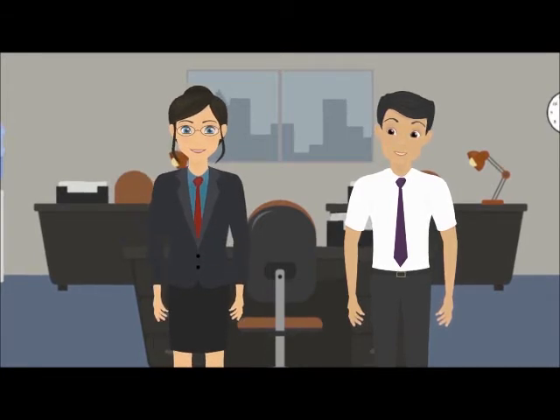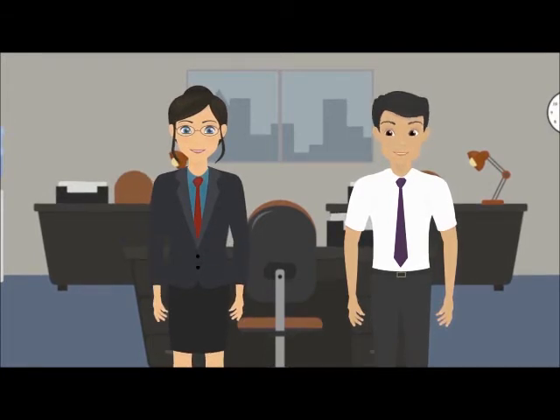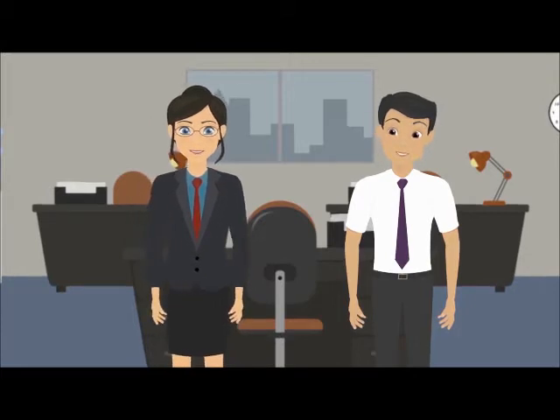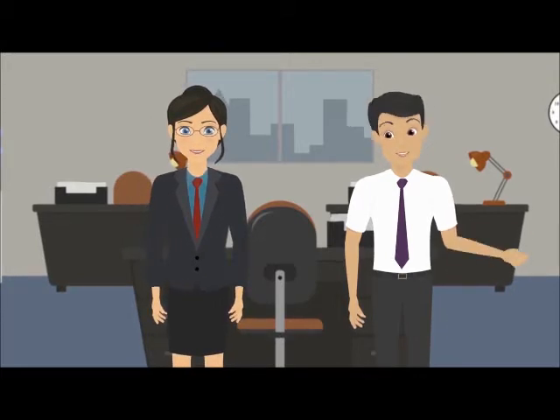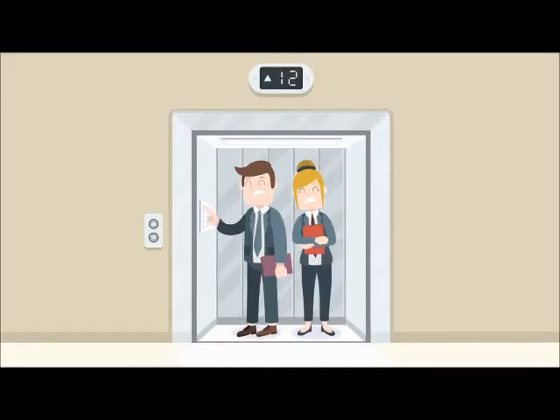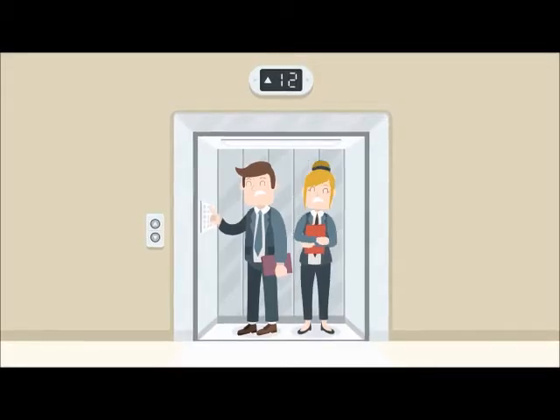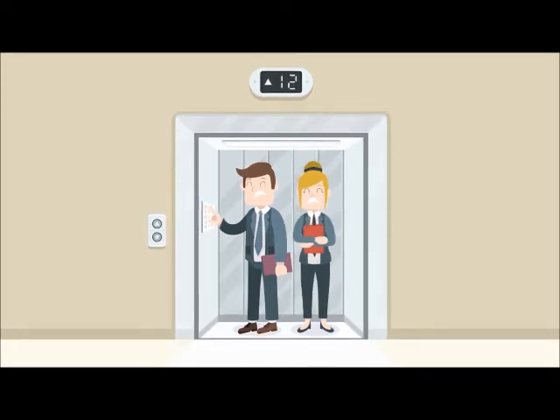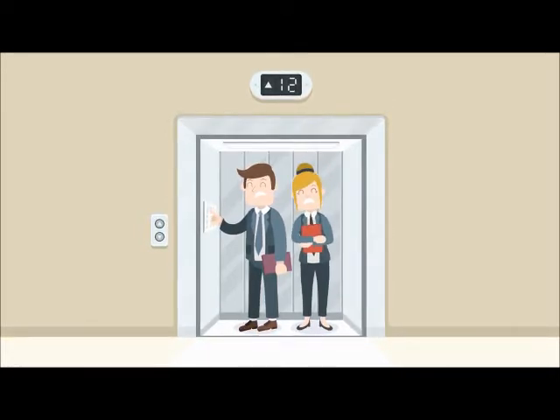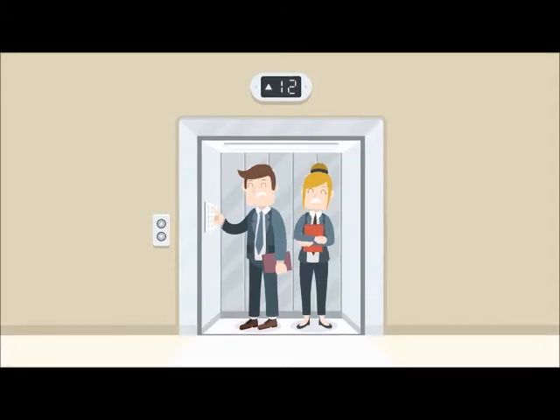What do you mean by failed dangerously? It means it failed to carry out its safety function of stopping closure and retracting the door when it sees a movement. Then there should be something called failed safely? Yes, Sheik, you were right. If the door sensor wrongly senses someone when no one is there between the doors and opens the closing door or prevents closing of the open door, then it's a safe failure.